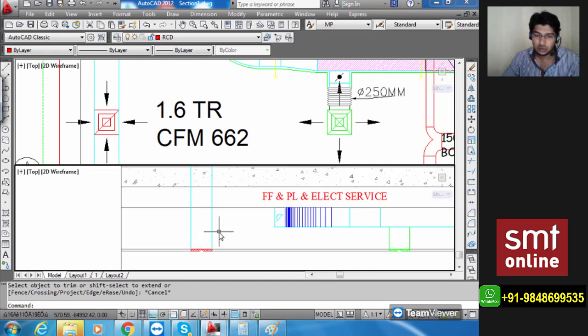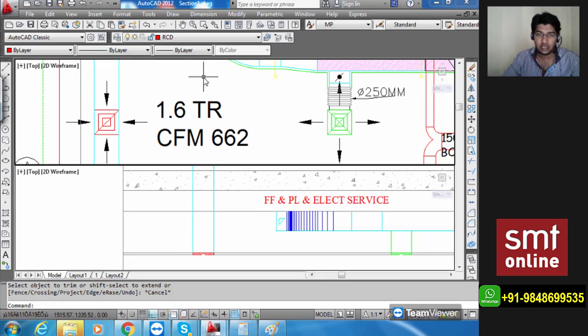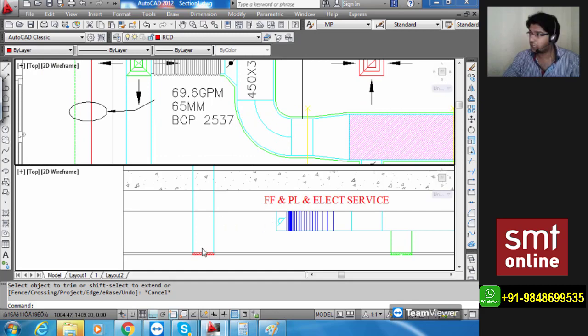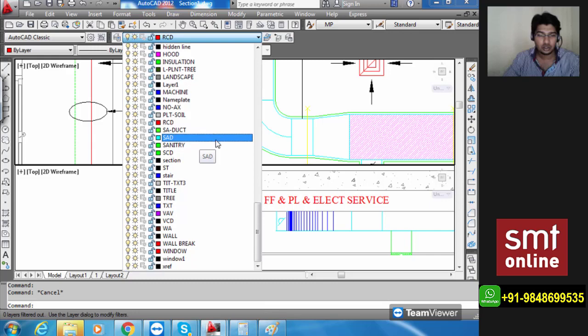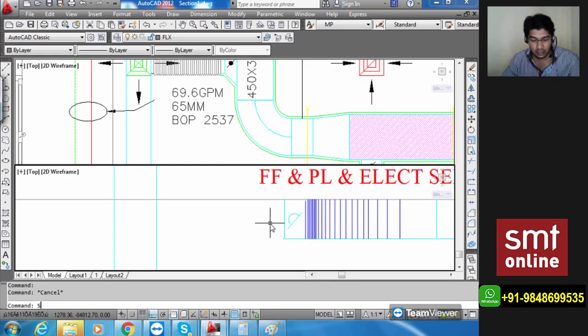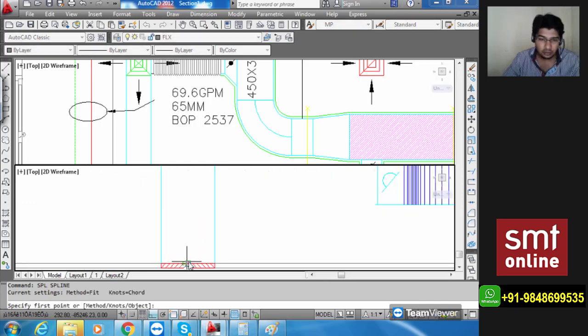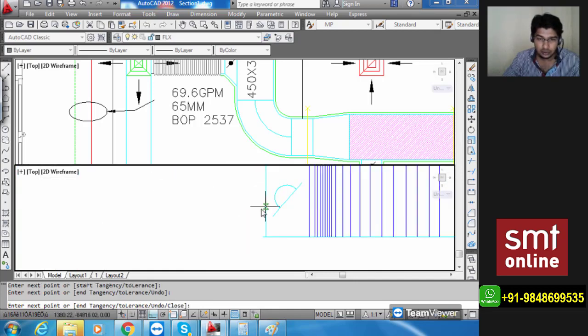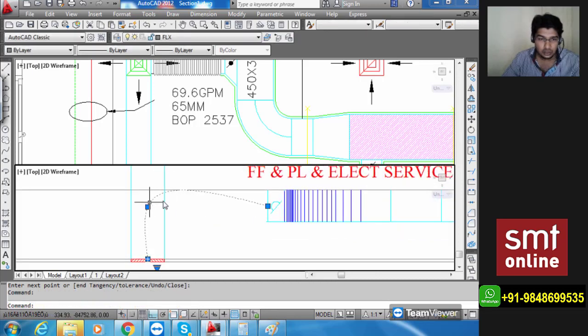And now I'm not going to show the duct, I'm going to show the flexible duct. So I don't really require this portion, but I will be deleting this after I capture my flexible duct. For drawing the flexible duct, I need to draw my spline, and then use the measure command. If I select this, it says FLX is the layer. I'm going to drop FLX, come into this, take my spline, start from the midpoint, take a turn, go here, try to join with the midpoint, press enter. Try to make that a little comfortable to view.